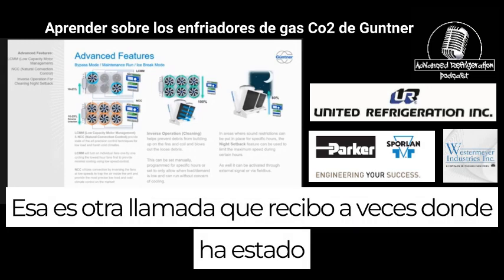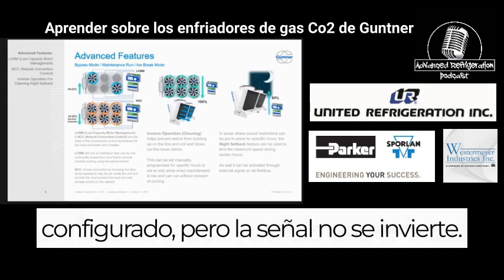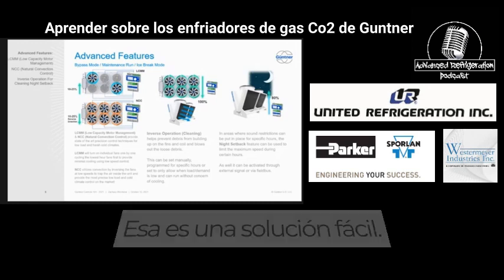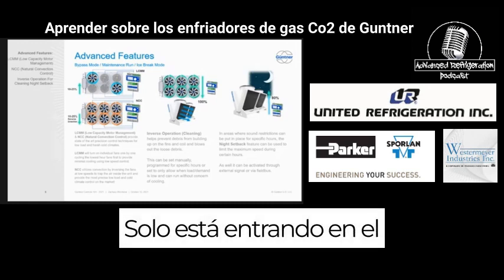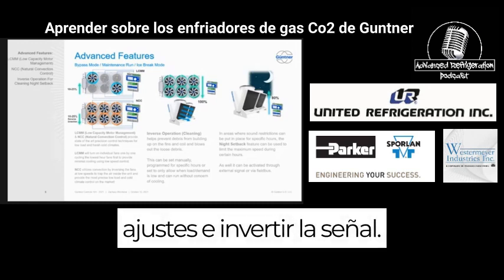That's another call I get sometimes where it's been set up, but the signal's not inverted. That's an easy fix. It's just going into the settings and inverting the signal.